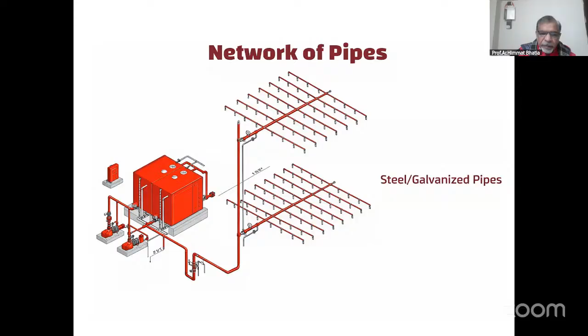All these pumps open with the sensor. The jockey pump is always connected to the electrical system, and as soon as it requires to open the water supply, the jockey pump starts and it starts the other pumps automatically, but you have to stop them manually. The fourth pump is a standby pump for the sprinkler water pump.